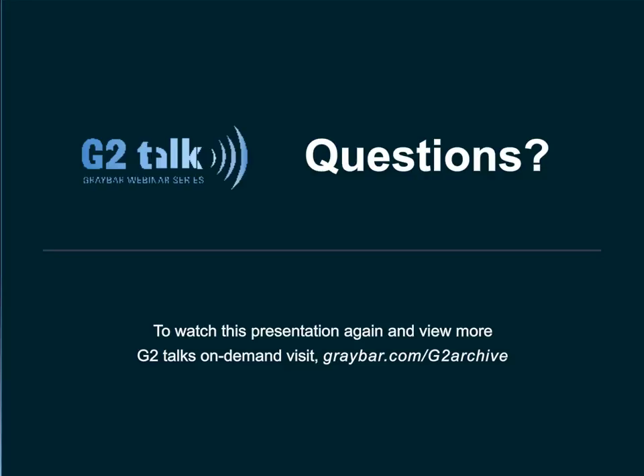Right. The next question is, why not just attach a plug directly to the horizontal cable for a WAP application? Well, that kind of falls back on the other question. If you're talking about Cat 6, that's something that could work well. But in my experience, the box cameras or the IP cameras where they have the RJ45 that connects directly out the back are great, but a lot of your dome cameras simply won't have the space available to accommodate a 6A plug. When you're talking about PoE reasons as well as bandwidth reasons, you've got to use caution with a direct attach field 6A plug.